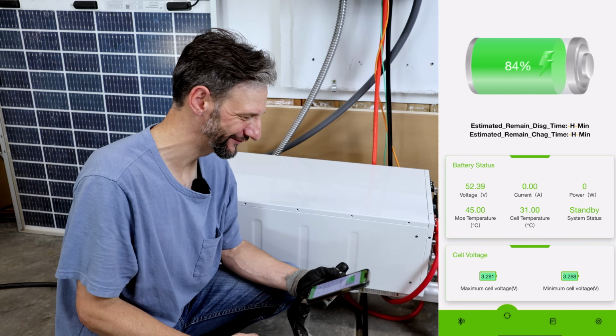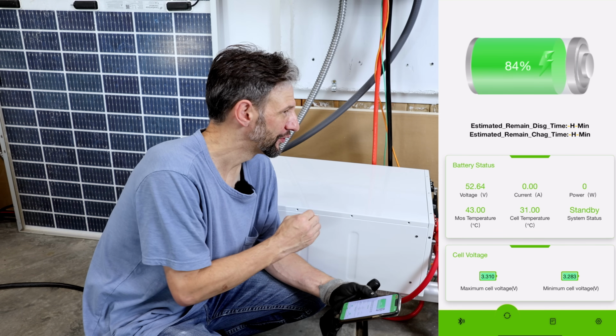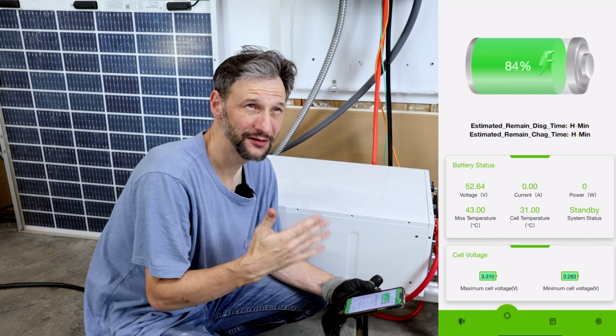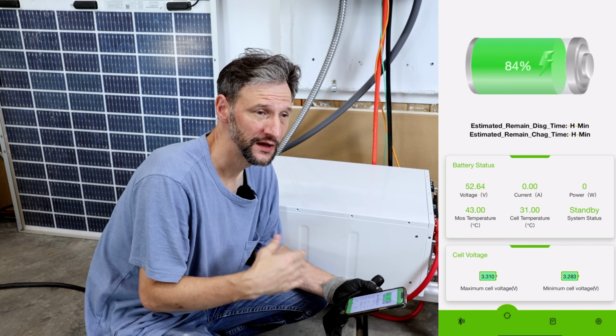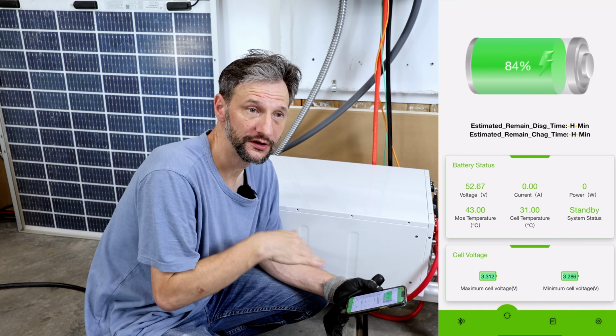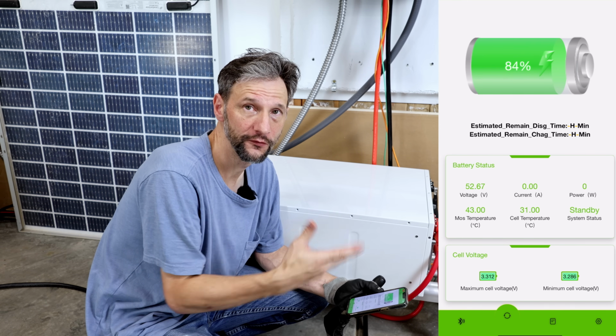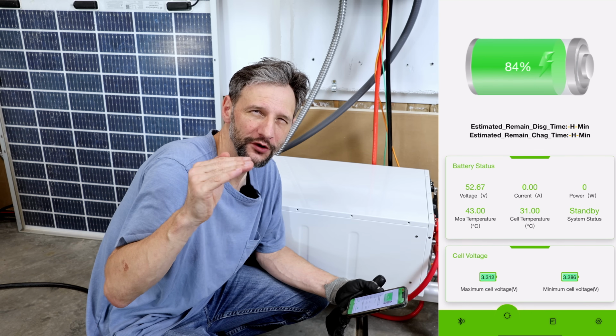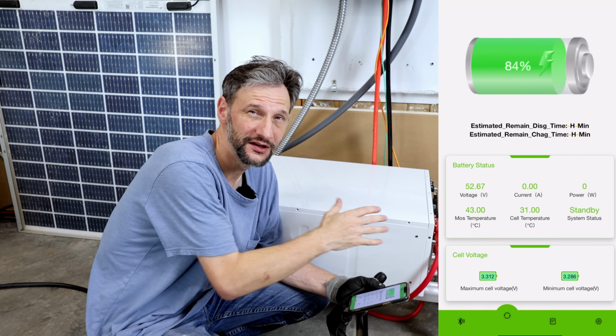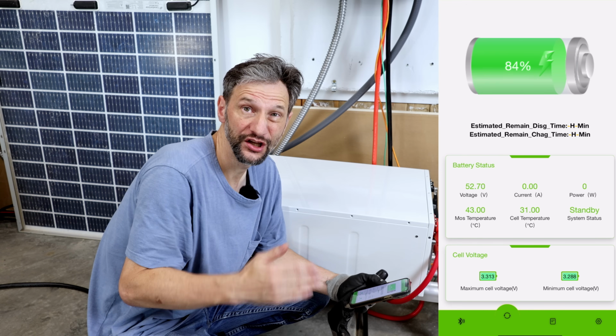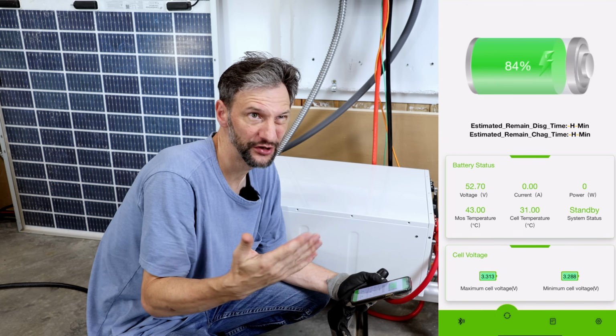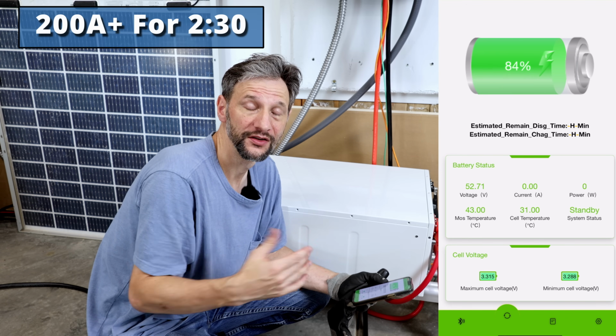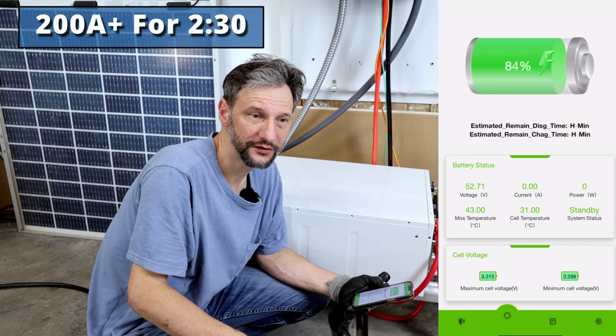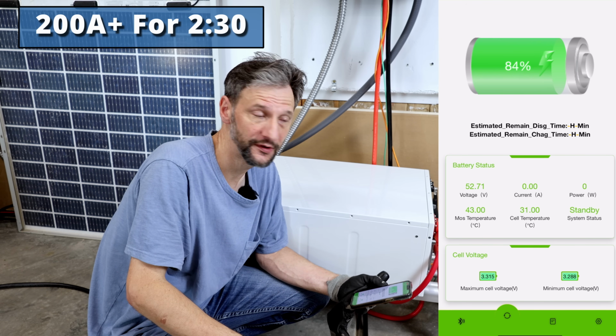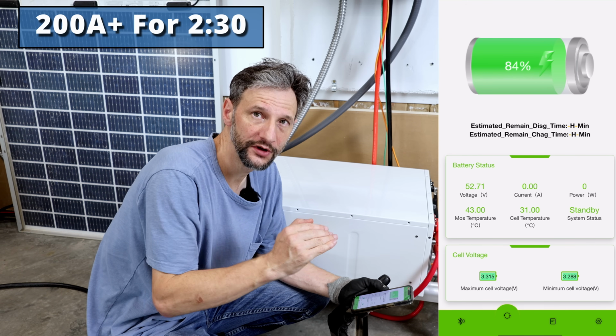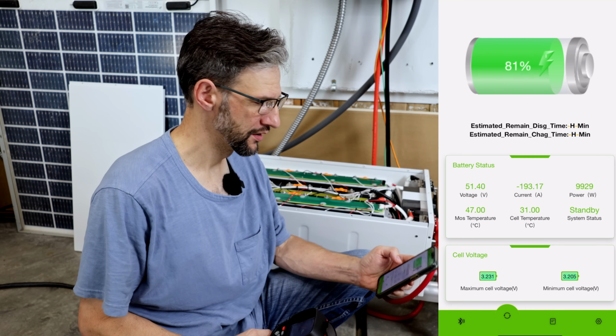I wasn't fast enough. All right, the BMS gave up. So we were running 210 plus amps there for quite a while. There's going to be a limit in the software that doesn't let it do that for very long so that it doesn't overheat things. So I'm going to have to run it just under 200 amps so we can see if there's any hot spots in here. But we ran it over its maximum 200 amps at about 210 plus amps for several minutes. I'll put the total amount of time here on the screen before the BMS stopped that activity. So let's try one more time just under 200 amps.